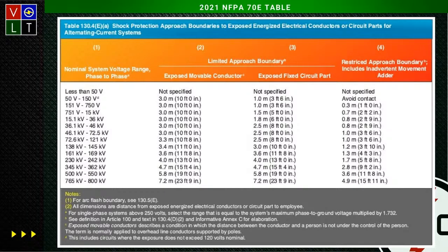Now I want everybody to listen to what I'm about to tell you: that right there is the very minimum your barricade can be. That's to protect you and unqualified personnel. Now if I look at the restricted approach boundary, it's going to tell you anytime you're within 1 foot—and right above that in the Fine Print Note 4—it's going to tell you this includes inadvertent movement. In other words, what we're telling you here is we consider that the same as if you're going to be working on the equipment, if you're within that distance of that equipment at that voltage. That goes into a little further detail explaining that.